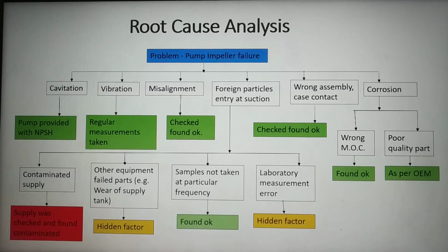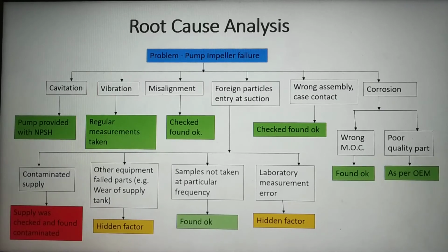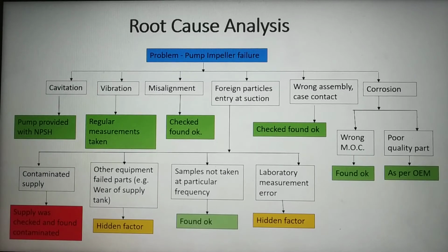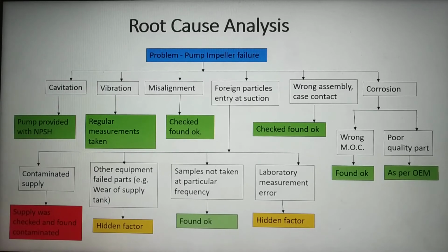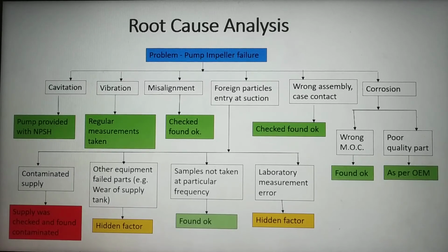Next is vibration. Regular measurements are taken, so this is also not the cause. Next is misalignment. It has also been checked and found okay, so this is also not the cause. Now fourth is foreign particles entry at suction. So from where, or what are the sources where the foreign particles can enter into the suction?